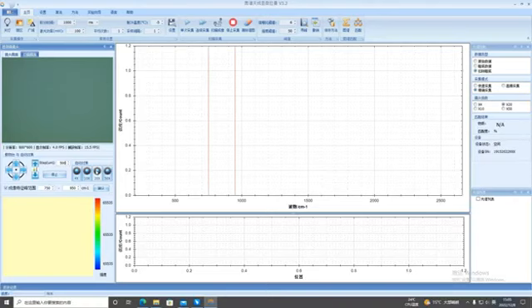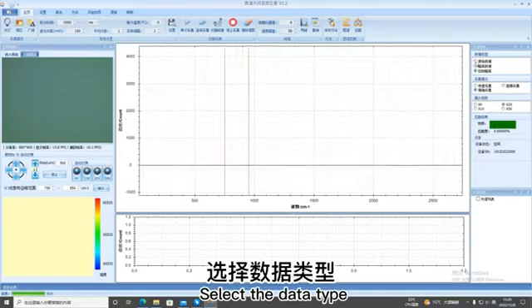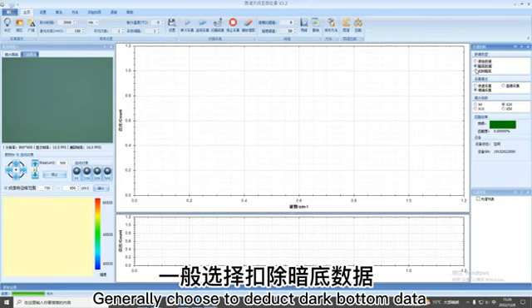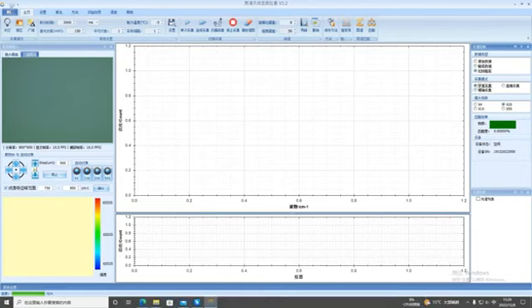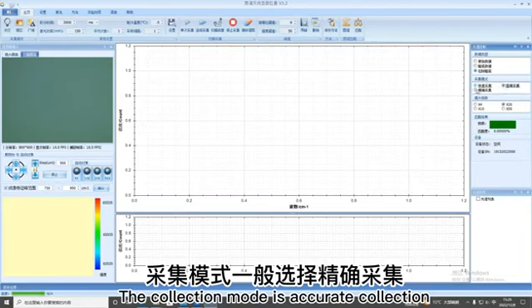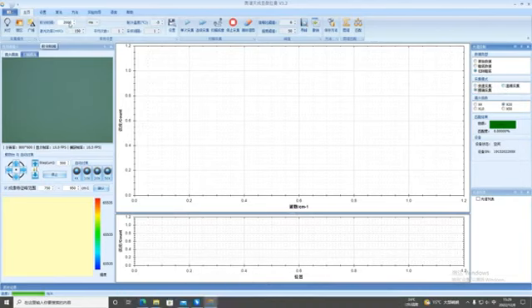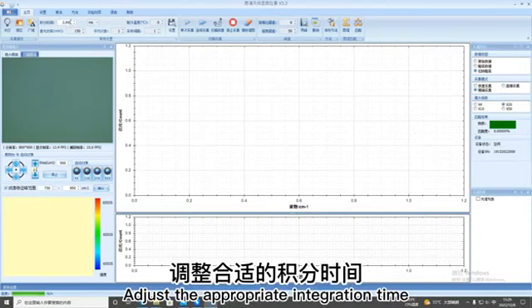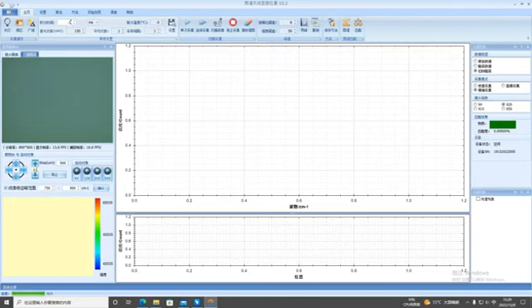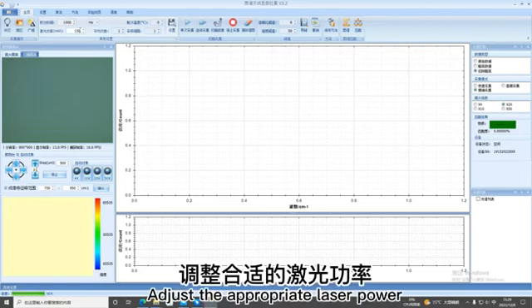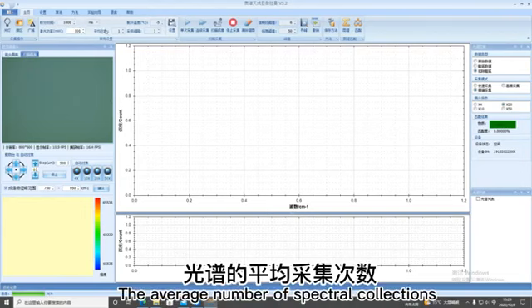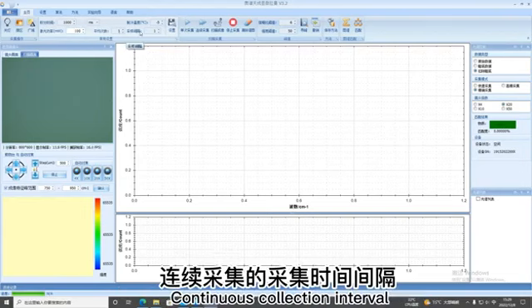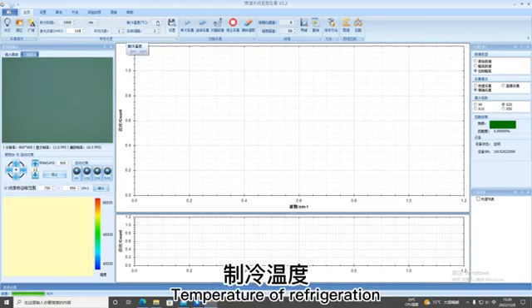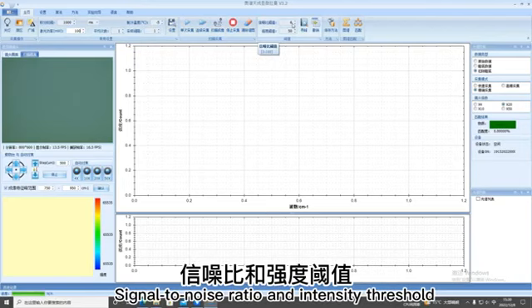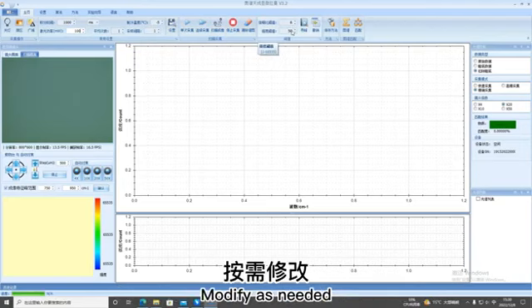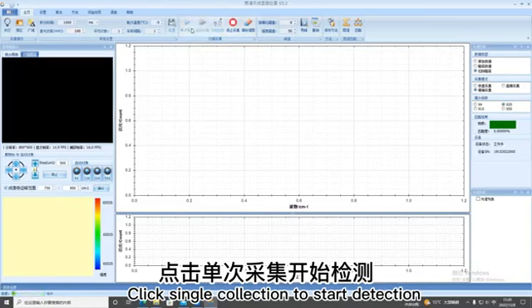Adjust parameters. Select the data type. Generally choose to deduct dark bottom data. The collection mode is accurate collection. Adjust the appropriate integration time. Adjust the appropriate laser power. The average number of spectral collections, continuous collection interval, temperature of refrigeration, signal-to-noise ratio and intensity threshold can be modified as needed. Click single collection to start detection.